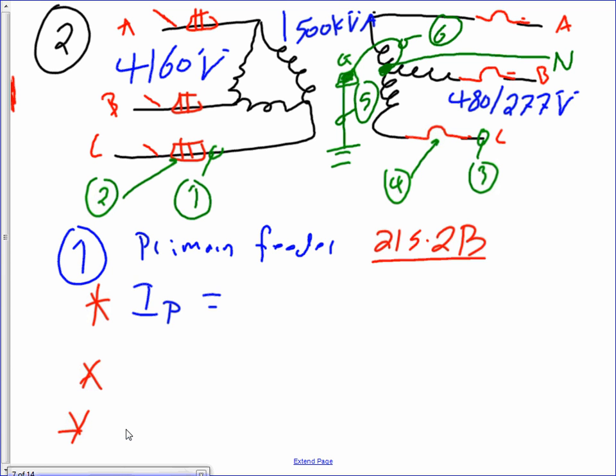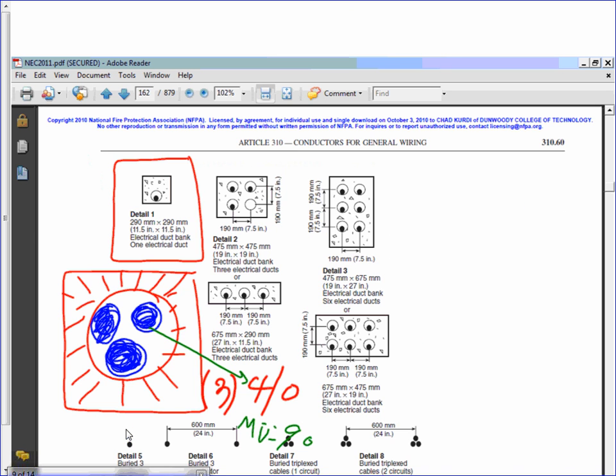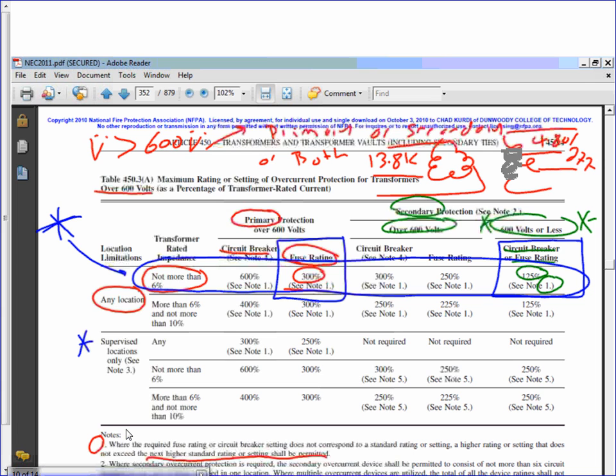6 things. Same way. The only thing I want you guys to pay attention to, you see the 4160, since this is higher than 600 volt, when we size the cables and the fuses, we have to go to a different table. Why? What makes this question different than the one before? Can you guys see the voltage? One voltage is higher than 600 volt. Okay? If you're higher than 600 volt, gentlemen, here's the table. Oops, where's the table? Okay, here's the table that we have to go to. If you're higher than 600 volt, this is the table that you're supposed to go to.